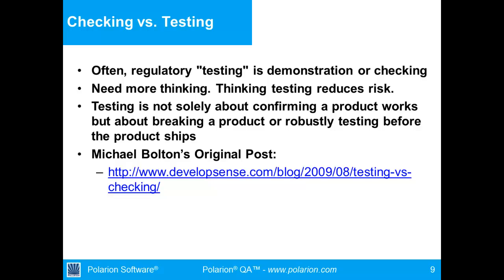In my area, the checking has a lot of value because you need to do checking of requirements in order to demonstrate conformance to the FDA regulatory requirements around requirements confirmation. But that's not the end. That's merely the beginning. There are lots of other aspects of what the FDA really wants: they want you to proactively examine the risk of the product at any point in time and address risk. And that's what testing really is, which is, I wonder what would happen if...